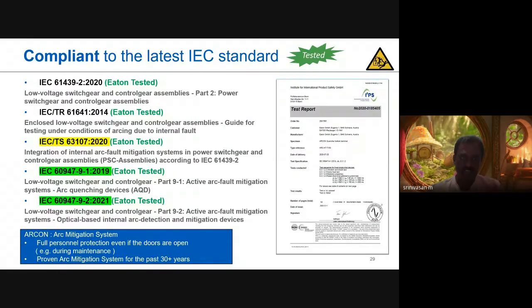There are some international standards. You might have noticed the very basic standard IEC 61439-2. For any project specification, we insist it should be type tested as per IEC 61439-2 for the MDB, SMDB, MCC and so on. One step ahead, in most project specifications we see the IEC 61641 requirement, mainly for internal arc compliance. Also, there are three new standards launched in the last 5-6 years. The first one is 63107.